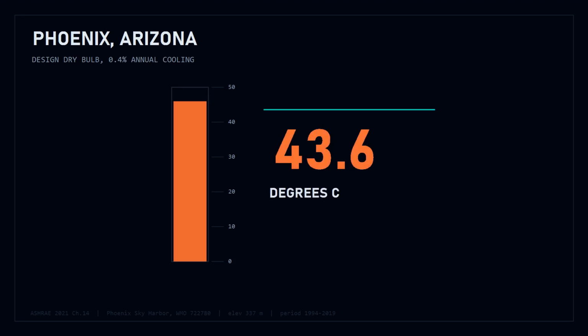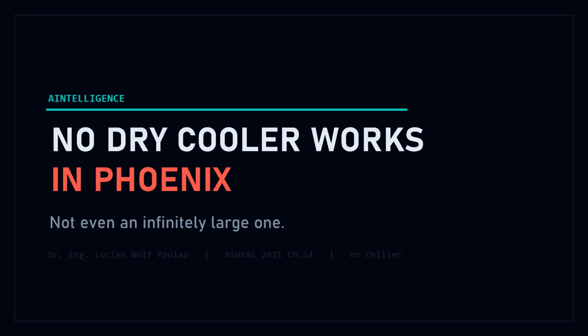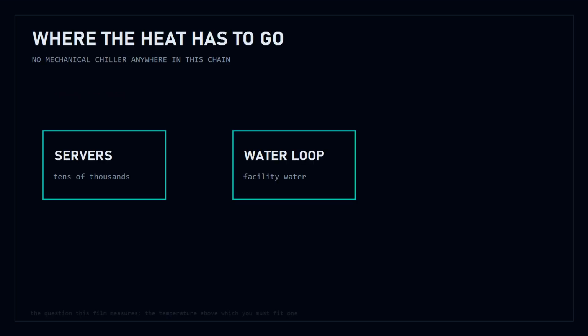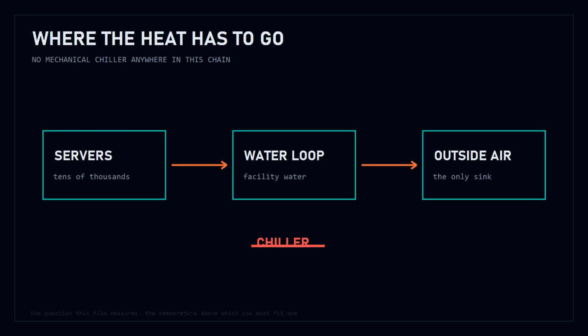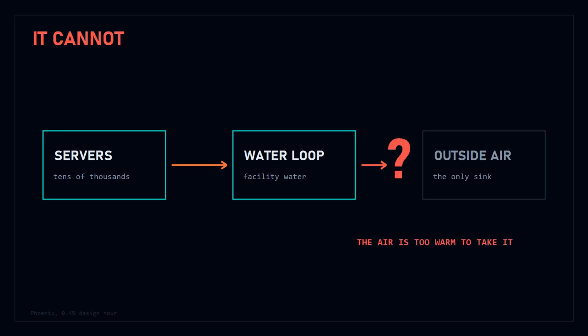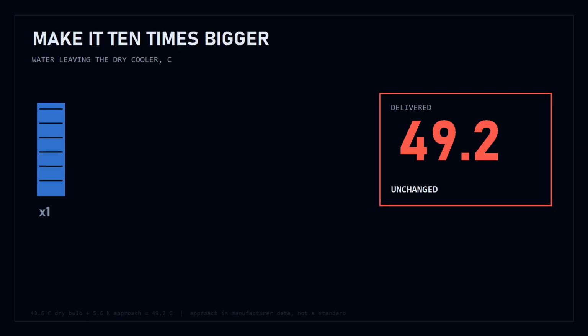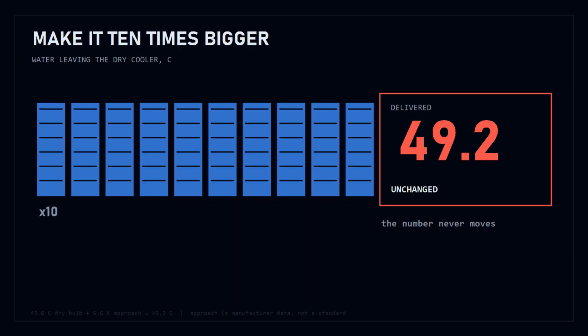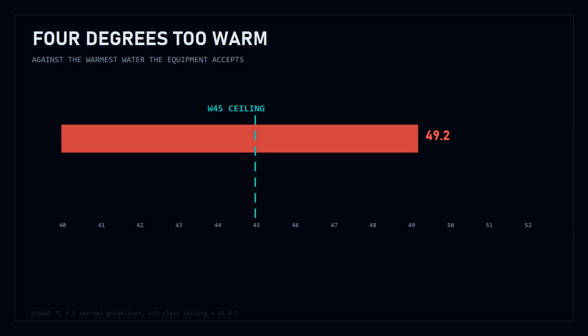Phoenix, Arizona, 43.6 degrees on the design day. And somewhere in that heat, a data center has to throw away the waste heat of tens of thousands of servers using nothing but the air outside. It cannot, and here is the part that should bother you. Making the cooler 10 times bigger does not fix it. The water still comes out at 49 degrees, 4 degrees too warm for the machines it is meant to cool.